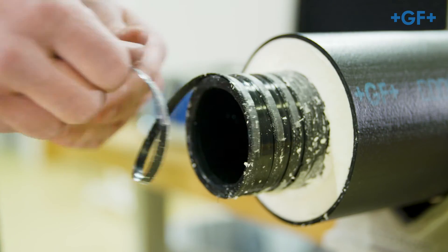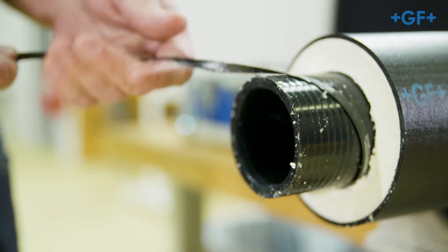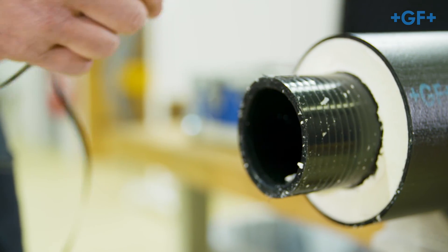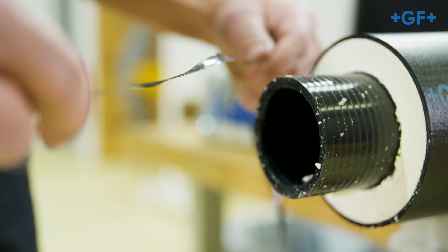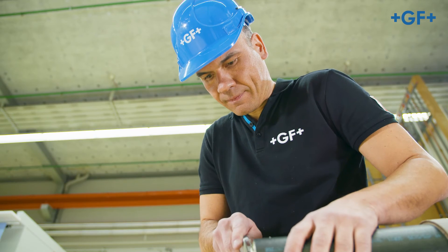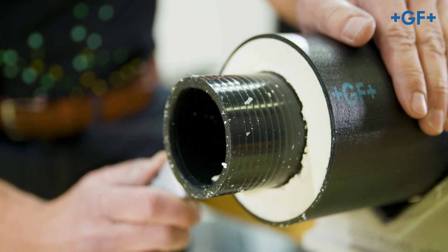Check that the inner pipe is peeled uniformly and completely and that the thickness of the chip is between 0.2 and 0.4 mm. Cut away the unevenly broken insulation face squarely without damaging the inner pipe.